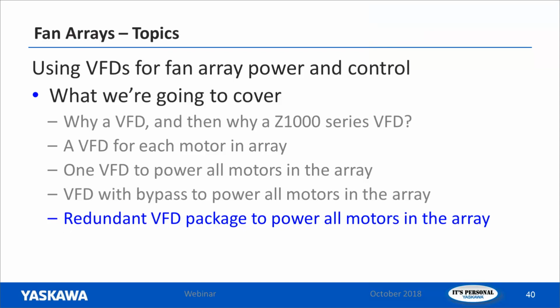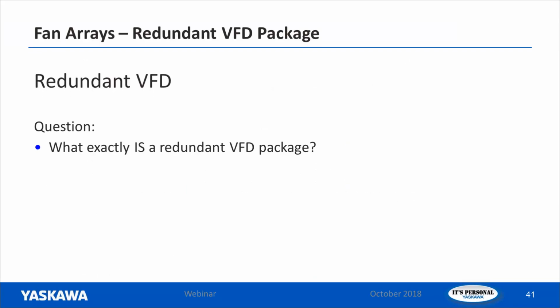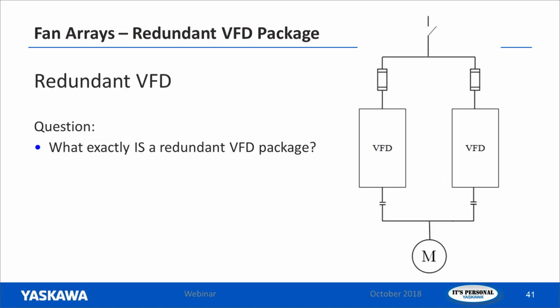So let's take a look at redundant VFD packages now to power all the motors in the array. And first, one question some of you might have is, what exactly is a redundant VFD package? So we're going to show schematically over here what it looks like. This would be what I would consider a generic run-of-the-mill redundant VFD package. We've got a disconnect switch here as the main power for the enclosure, and then we've got VFD-A and VFD-B, and each one of them has its own fused protection on the input. And down here we have our isolation contactors, so that when we're running one drive, we're not backfeeding power into the other. And of course there's one motor in this particular example that they'd be running, because this is just a standard redundant bypass package.